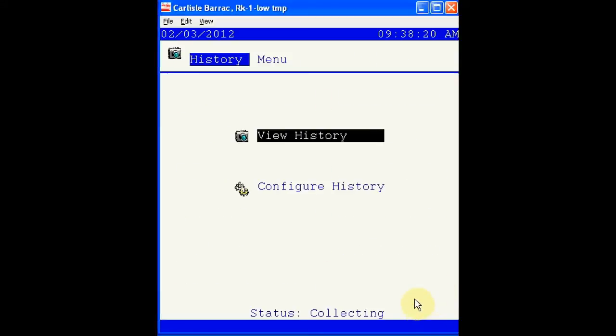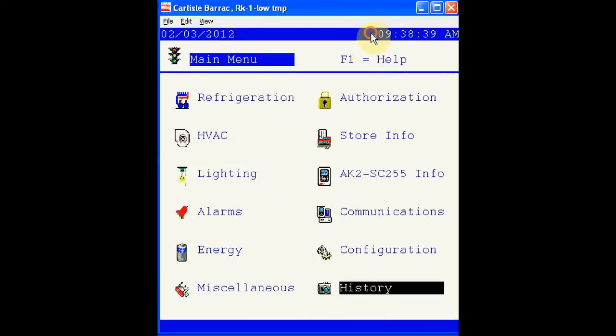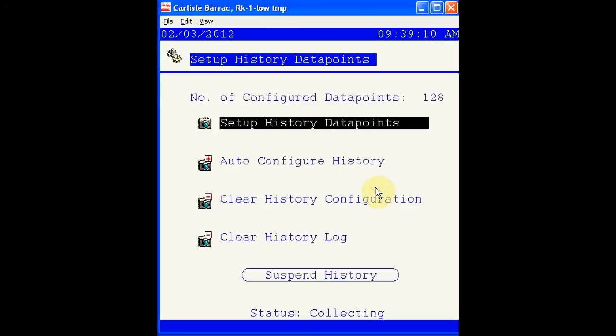Here we see that history is being collected. Other status you may see are not configured or suspended. History can only be restarted if found in suspended mode with a supervisor access code. It's possible to verify that points are being recorded in history by selecting Configure History.